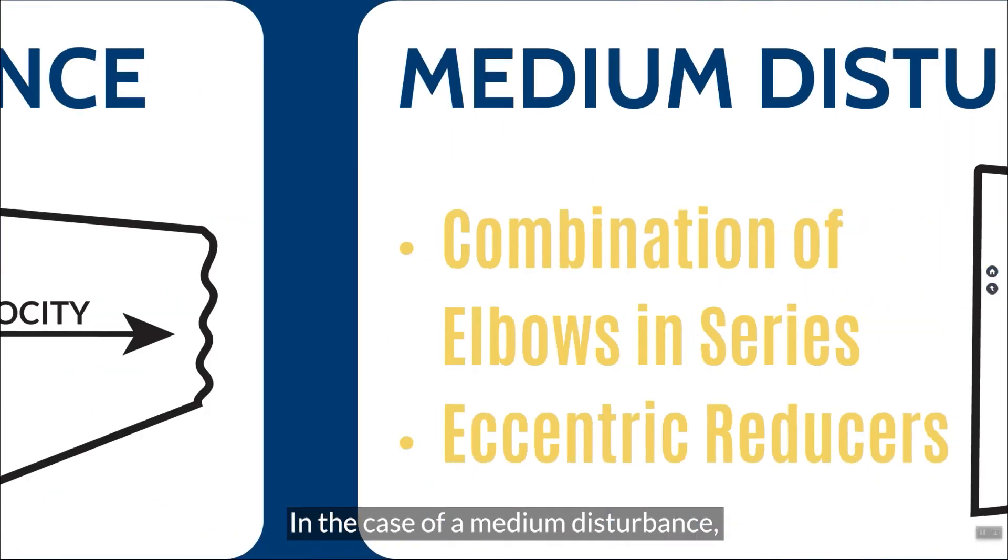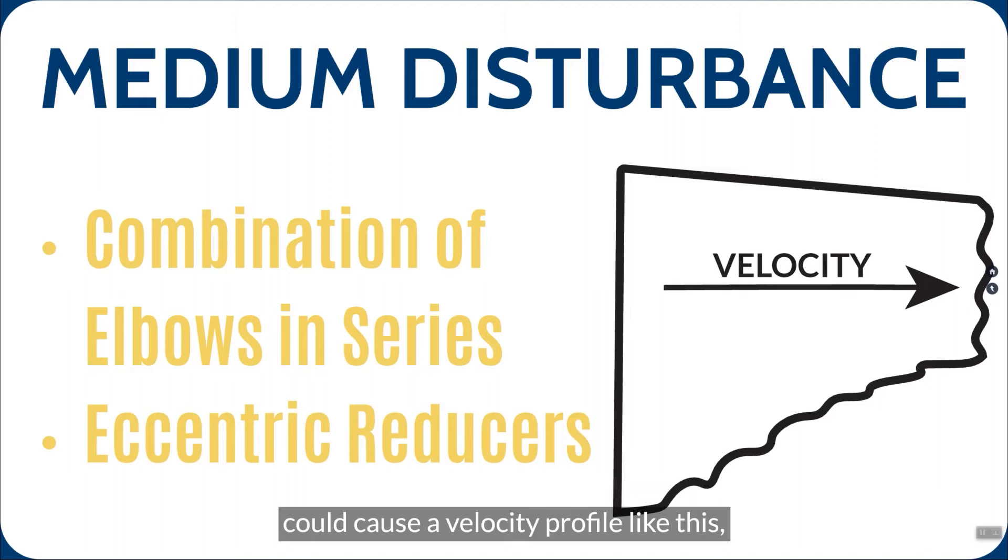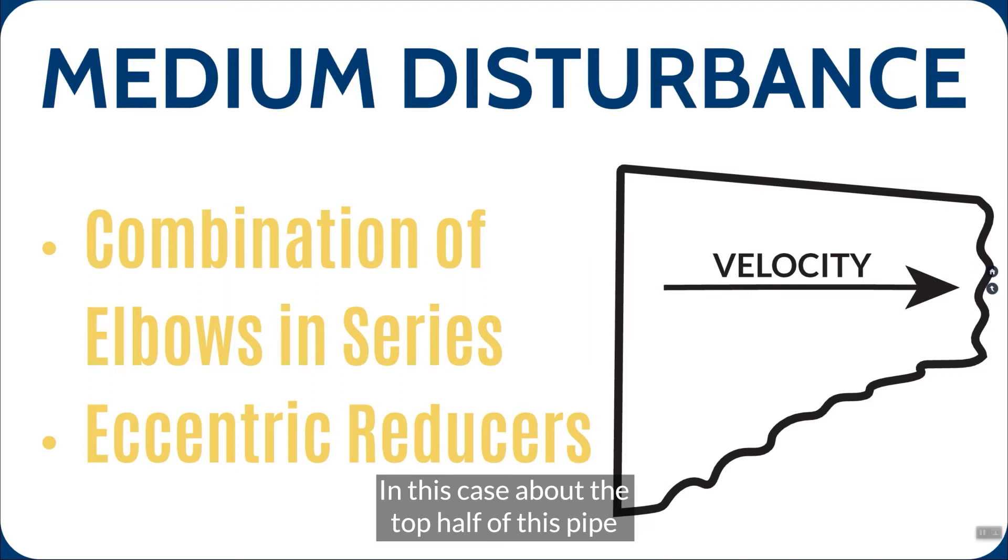In the case of a medium disturbance, things like a combination of elbows in series or maybe an eccentric reducer right in front of the element could cause a velocity profile like this. It may be a medium disturbance. In this case, about the top half of this pipe is moving steady. That's about the same velocity, but then you get this slow degradation of velocity as it moves towards the bottom of the pipe.